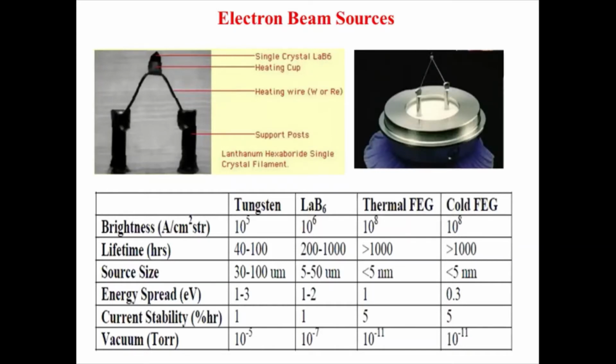In short, 30 to 40% more amount is to be paid if you want to change the source, because the resolution offered by the scanning electron microscope with thermionic gun is say 50 nanometer, then with field emission gun you have a resolution of 5 nanometer. So there is an increase in the resolution by an order, and for that you have to pay more.